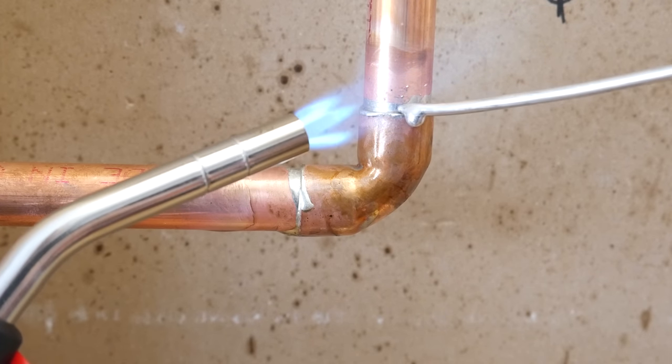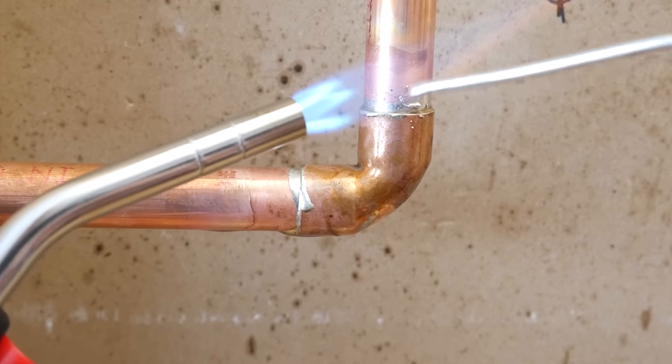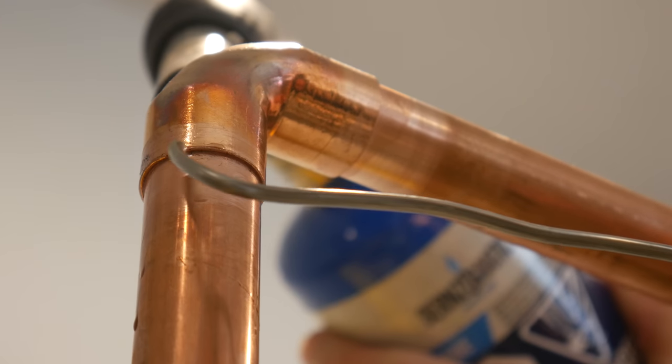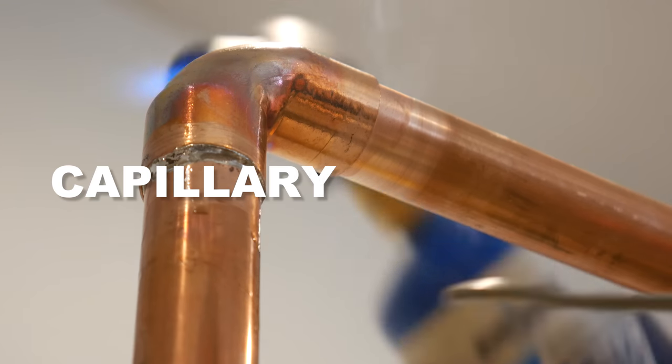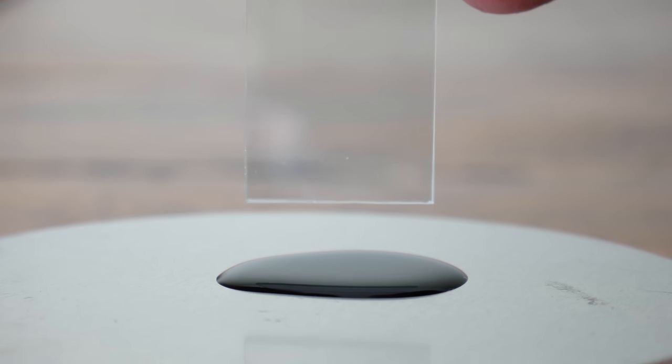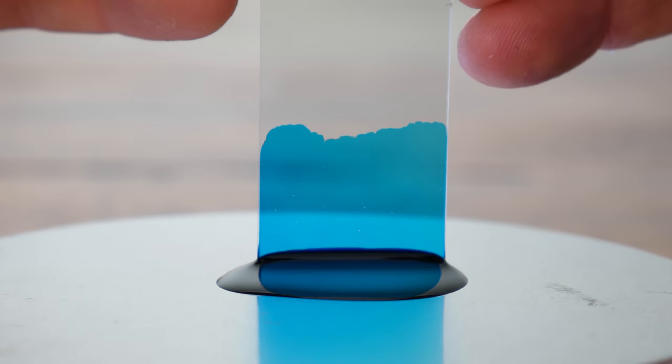Number three is a mistake I see a lot when a beginner solders, and that's to heat the solder and not the actual pipe. To solder a joint properly, the fitting must be heated for a phenomenon called capillary action to take place. Capillary action, when soldering copper pipes, is what ensures that the joint is entirely filled.